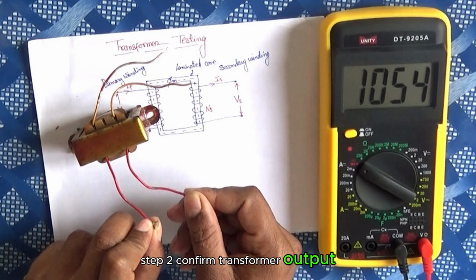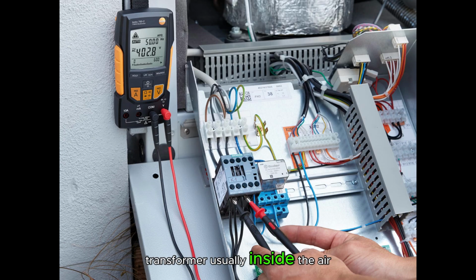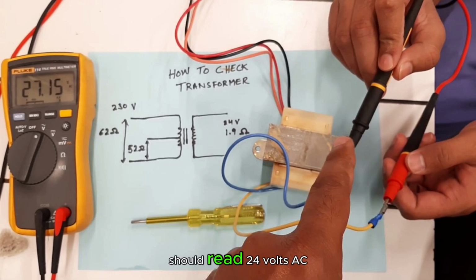Step 2. Confirm transformer output. Go to the low voltage transformer, usually inside the air handler. Check the input. It should read 240 volts. Then check the output. It should read 24 volts AC between R and C. If it's not producing 24 volts, the transformer may be burned. Replace it and keep going.